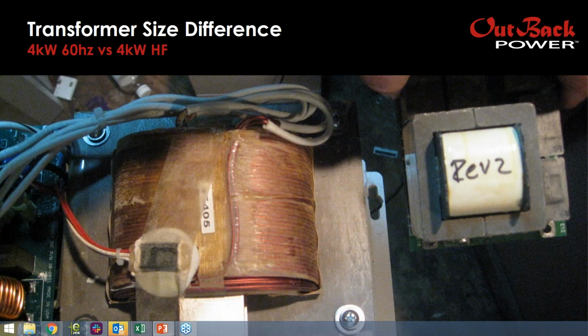You see a lot about low frequency transformers versus high frequency transformers. This is just a picture showing some scale. The one on the left is a 60 hertz, 4,000 watt transformer. It's about 35 pounds. And the one on the right is a 40 kilohertz high frequency transformer used in a high frequency inverter. That just shows that as the frequency of the inverter switching goes up, the physical size can be brought down pretty significantly. The downside is that the output's not directly usable, so it has to be converted again.